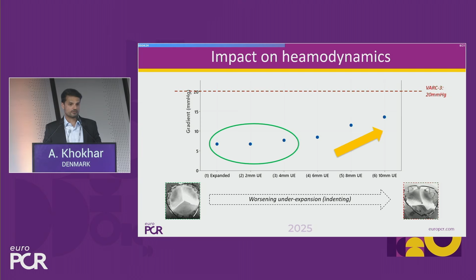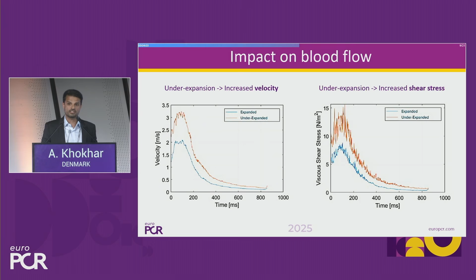So in blue, we've got well-expanded valves. In orange, you've got underexpansion. And you can see that in the underexpanded scenario, you've not only got increased velocity across the valve, but that also then translates into increased shear stress upon the leaflets, which again is then associated with formation of more thrombi.